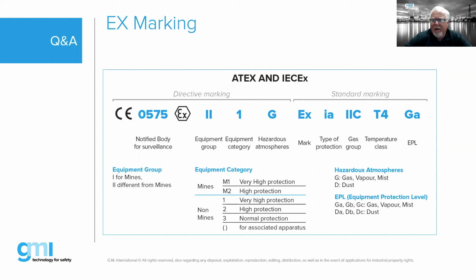And then finally our IEC EX EPL GA, which is telling us basically the same information that is told under the ATEX directive of 1G. So GA is telling us it's suitable for zone 0, zone 1, and zone 2 for gas applications. Sometimes you find combinations on the same certificate. The device might have several certifications combined, and the marking gets a little more complex than this. Absolutely.